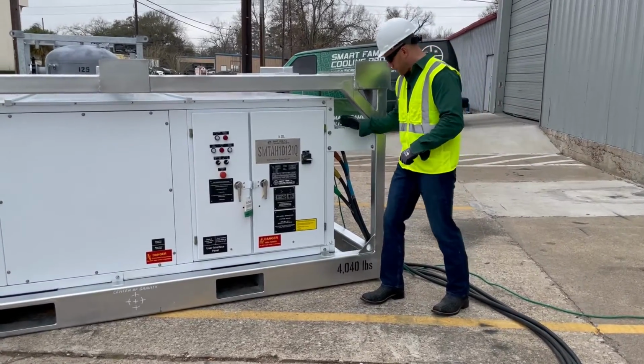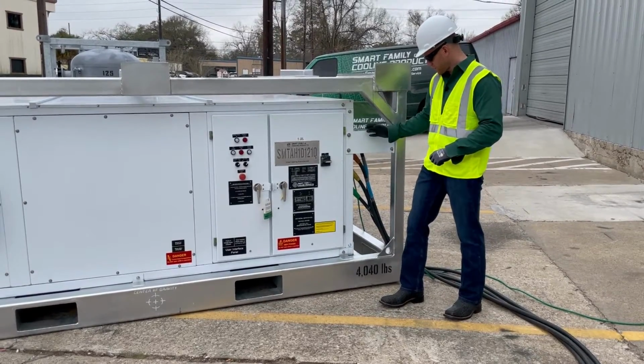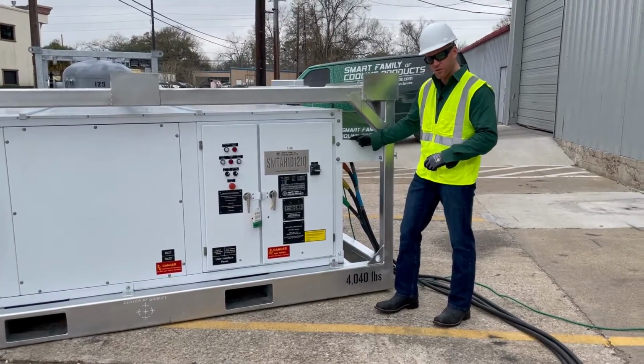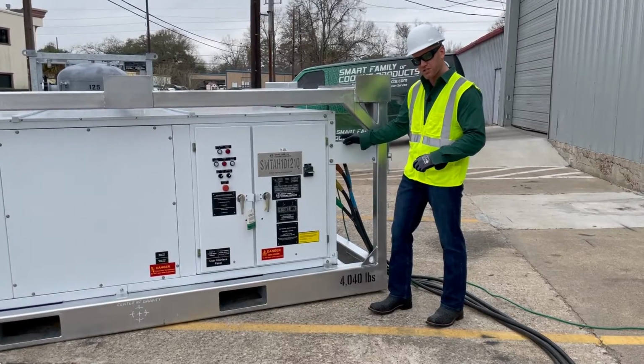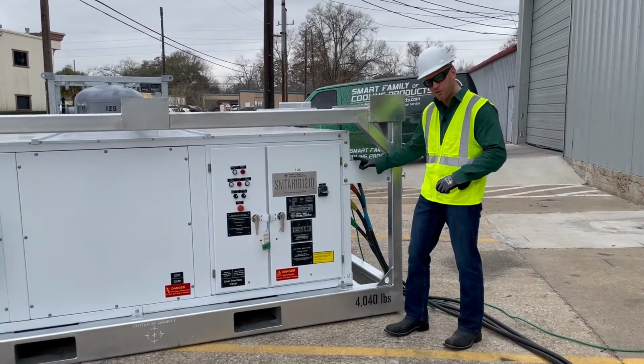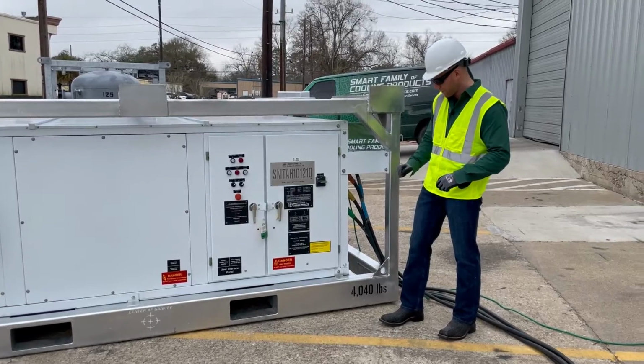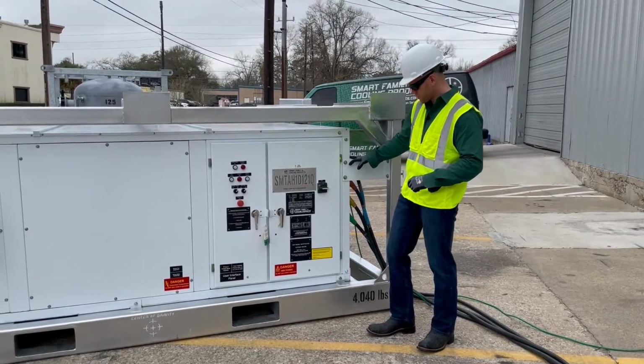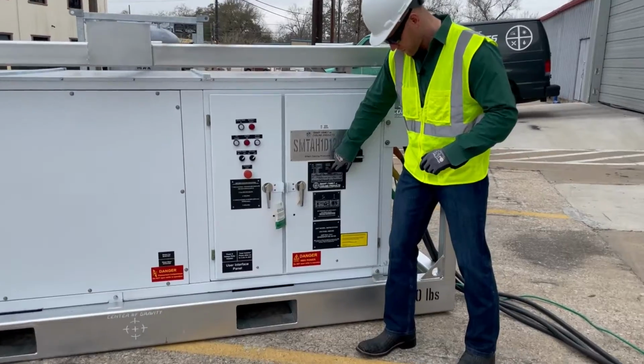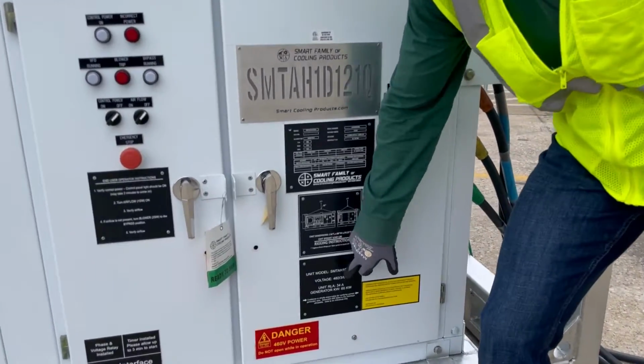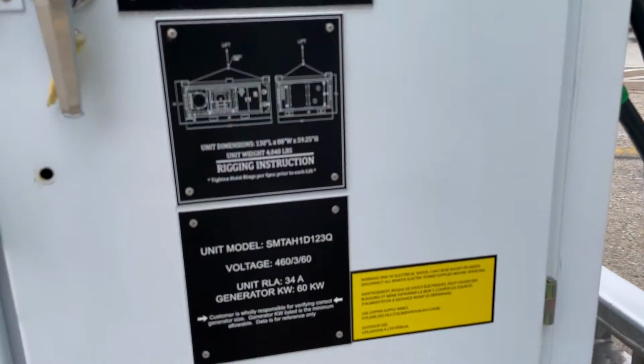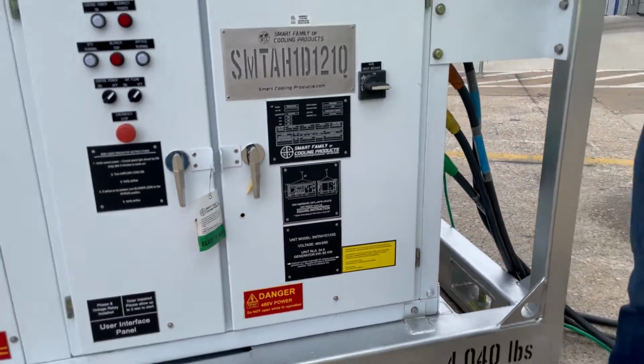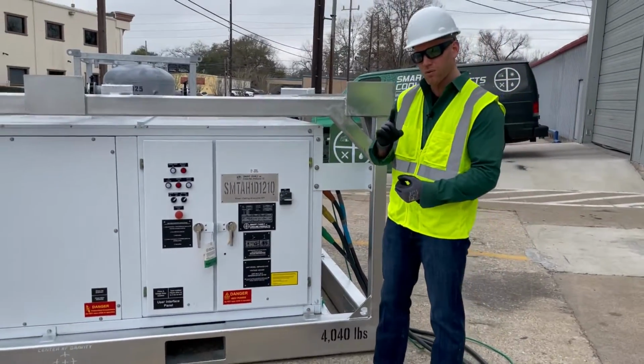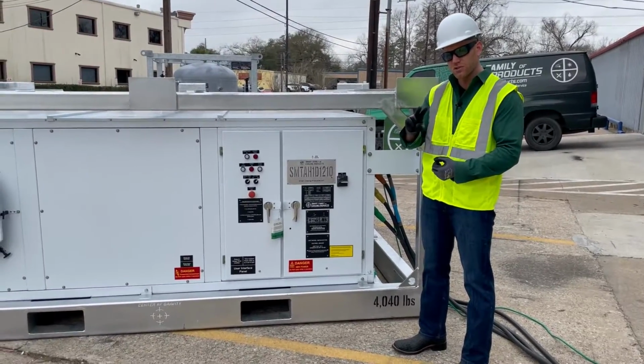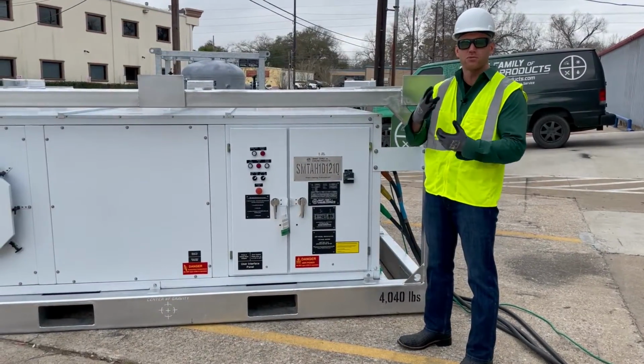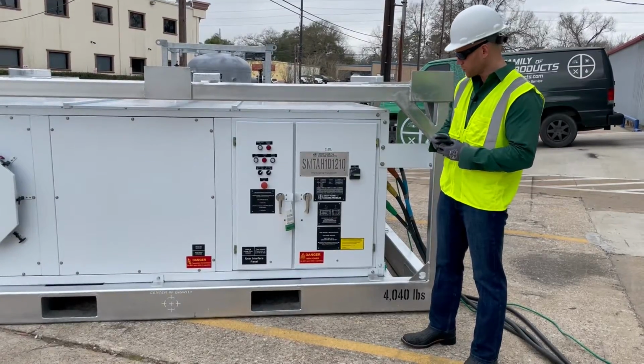This particular model has Series 16 cam lock connections here. You can tell very clearly that this is a 460 volt unit because we have 460 volt color coded cam locks, meaning brown, orange, yellow, and then our green. I could also tell what voltage this machine is by looking at the nameplate and or our generator tag. So we typically have tagging on these packages that tell you exactly what the power requirements are, how many amps this unit will draw, and what the minimum generator size is if this was running on portable generator power.